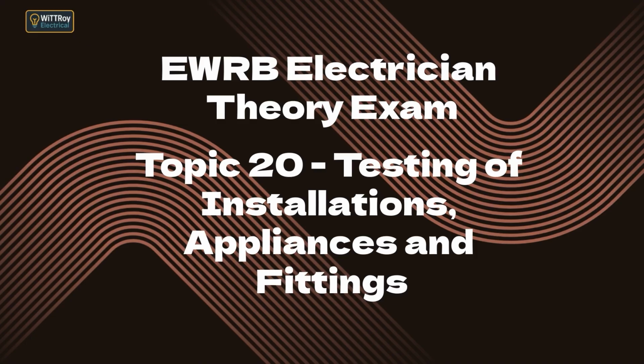Topic 20b. Explain that visual and mechanical checks of the installation are required by AS/NZS 3000 prior to instrument testing. Explain that this is done to ensure that all the specific requirements for issuing compliance certification are satisfied. Before any instrument is used, AS/NZS 3000 requires a full visual and mechanical inspection.